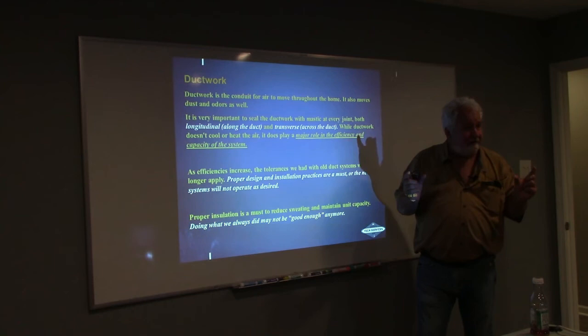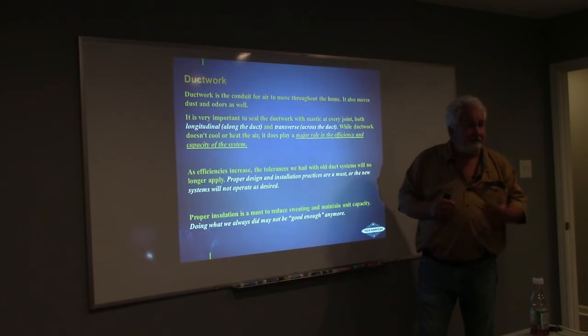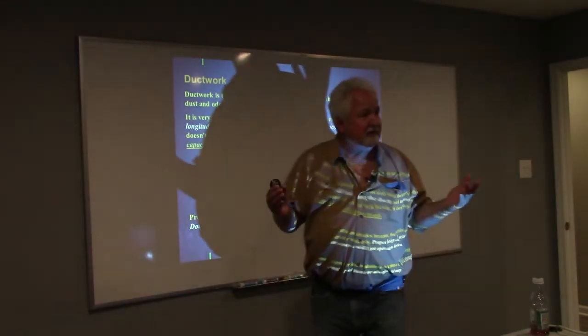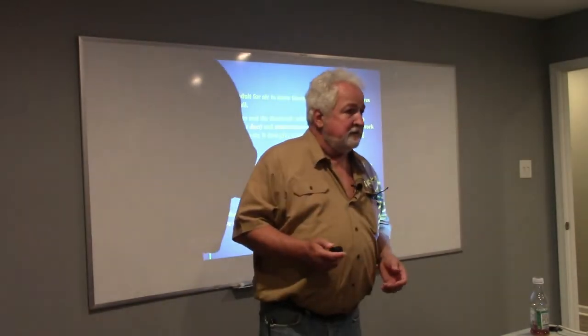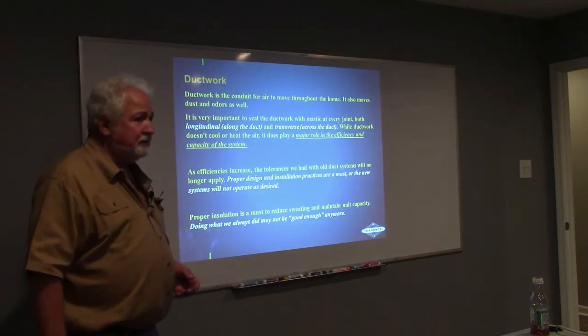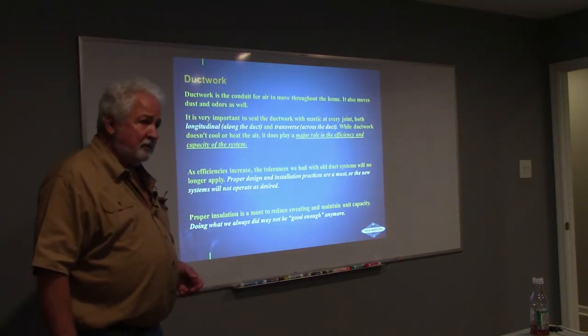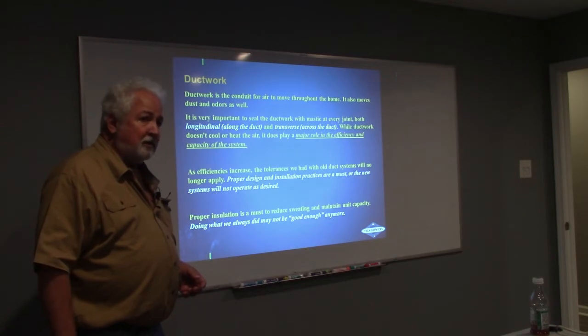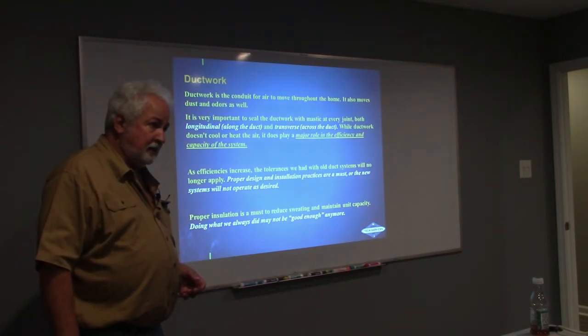Fast. Yes. If I have an R8, can I slow it down? Yeah, so it's going to take longer. Same thing with the moisture. Now, if it takes longer to get there, I have less chance of that ductwork sweating. So pay attention to that as we move forward. If you're going to be doing a lot of variable speed equipment, you want to start looking at R8 ductwork.